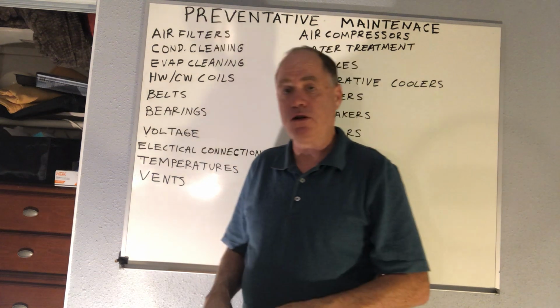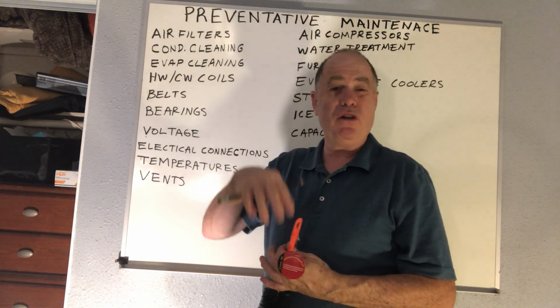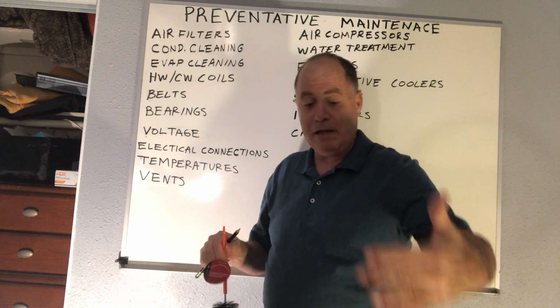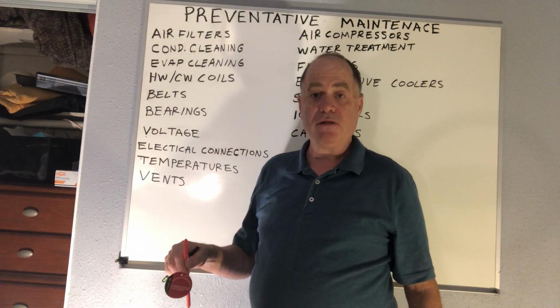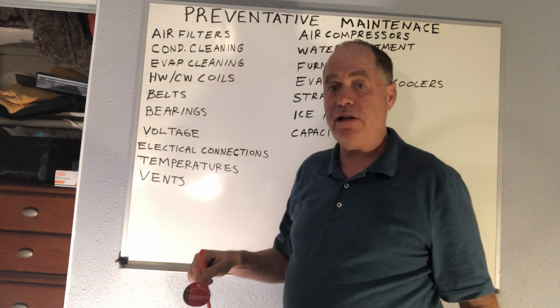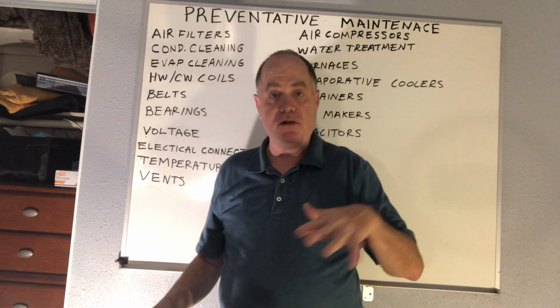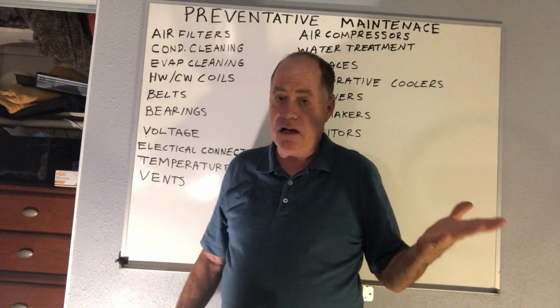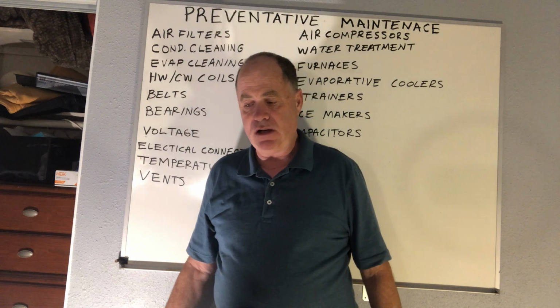cleaning of your condenser. Now, you can use a wet dry vac and a brusher, but you can also take some compressed air or something and then put plastic on the other side to clean your condensers, but you want to make sure you don't fill the whole area with dust. But if you can use some water and then vacuum it right up and use a lot of towels, that would actually get it the cleanest. But you probably may not going to be able to do that in a restaurant when people are around, okay, for slippage and things like that.